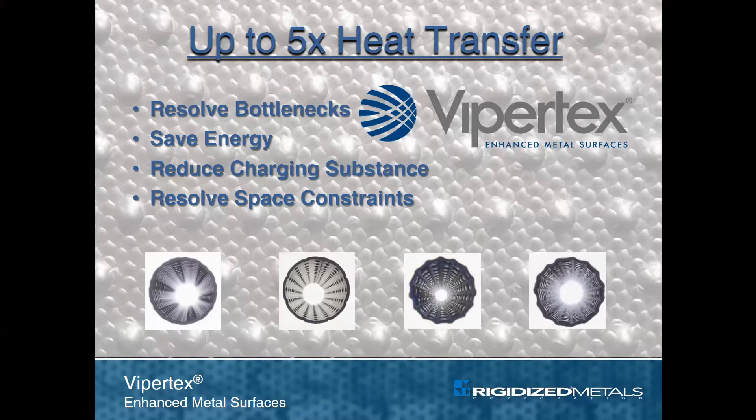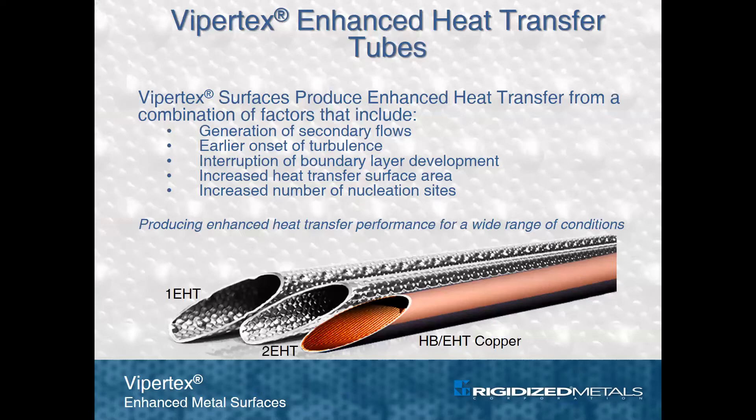With these enhanced surfaces, it is possible to achieve five times the heat transfer compared to smooth tubes. This impressive heat transfer performance is achieved from a combination of factors that include generation of rotating secondary flows, earlier onset of turbulence, and interruption of boundary layer development which promotes a higher temperature gradient at the tube wall.